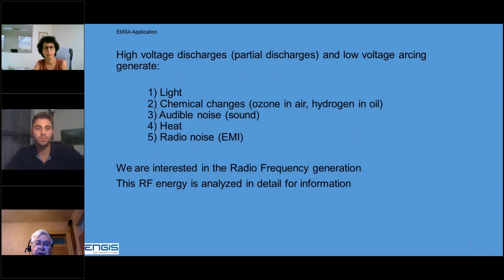High voltage discharges are usually considered a partial discharge. That and low voltage arcing, where there's current flow, produces light. You can see the discharge, the spark. Ultraviolet is also produced. There are chemical changes. Ozone will be produced in air, O3. Hydrogen is produced if the discharge is under oil. There's a sound produced. It can be an audible noise. You can hear the sizzling of corona. Ultrasound is produced. If it's really bad, like an arc, you'll produce heat, so infrared can detect it. And there's radio noise produced, EMI. And that's what we're going to be talking about, the radio noise, or the EMI.